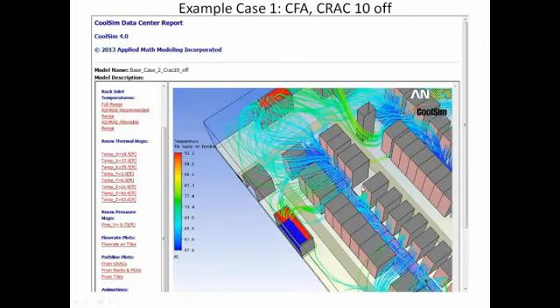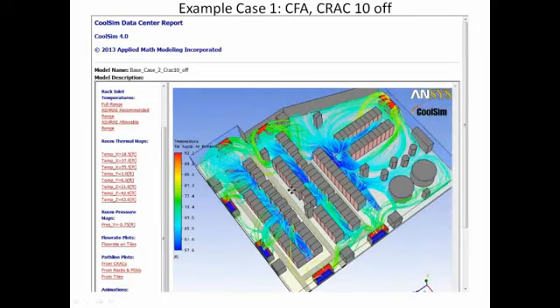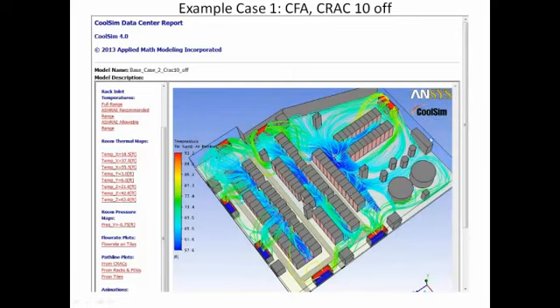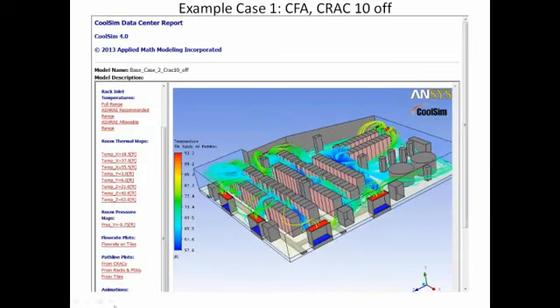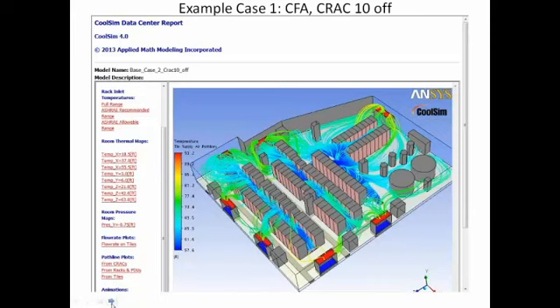But from a sort of a data center optimization point of view, this data center behaves better with this CRAC unit off than with it on, which I thought was kind of interesting. Not something you would predict. Now, it would be important for a full study to continue to go around the room and shut more of these units off as you go, because then you'd get an idea of what each of the failure mode conditions are, and it would give you a feel for where you could add capacity in the room without getting in trouble, which is another important thing to know.